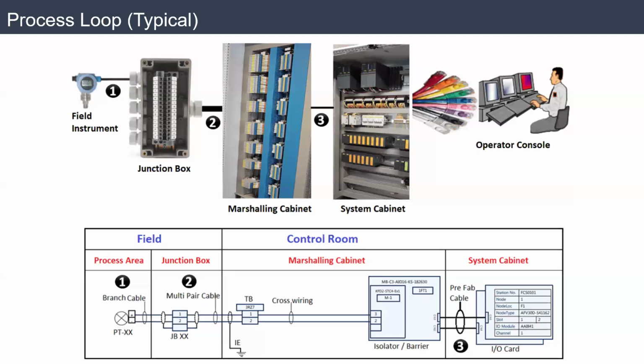So for each individual instrument, you will have this kind of table. Number two, the junction box: you will type the junction box number and in which terminal block these two cables are connected. So for example, here number one and number two. And again, from the junction box going to the marshalling cabinet inside the control room, in which TB, mentioning TB number 1 and 2 and how it's connected. Then if there is, for example, a barrier or isolator, again, how it's connected. Then in the system cabinet, where you will have the controller, and in the IO cards, input, output cards, where you will have analog input card, analog output card, or digital input or digital output card.